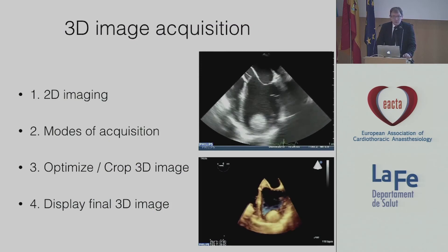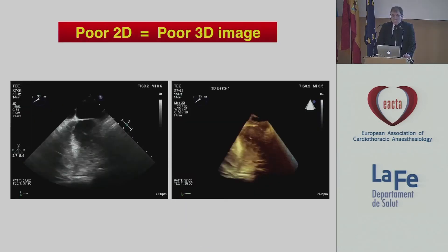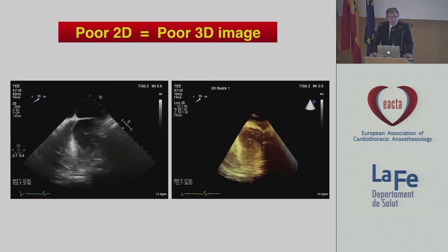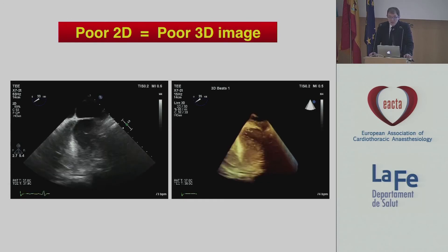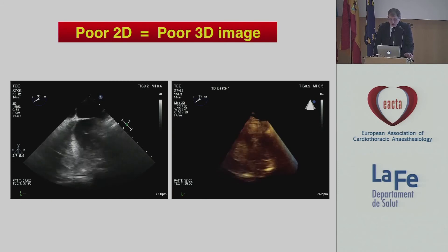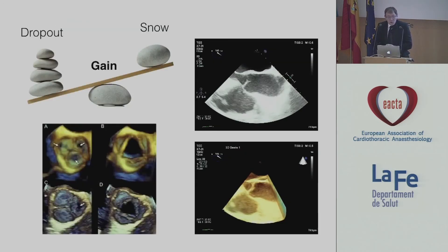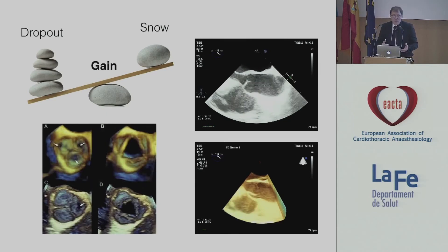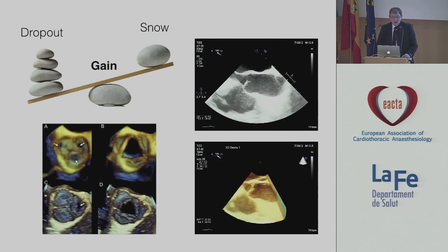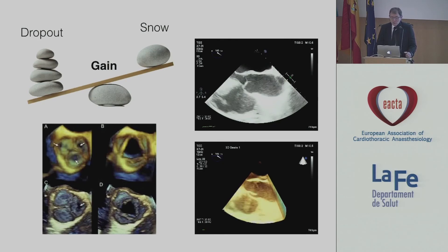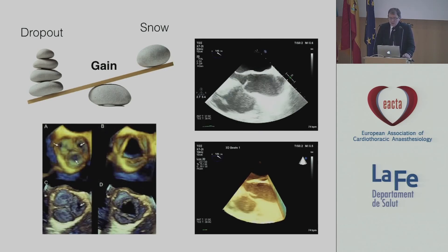This is a short outline of my presentation. Of course, the first thing you need to do before acquiring three-dimensional echocardiography data sets is to acquire good 2D images. Poor 2D images means poor 3D images. Try to optimize your two-dimensional images by adjusting the gain and the compression — it's a balance between under-gain, which gives you dropouts in 3D as you can see here pointed out with the white arrows, or too much gain, which gives rise to snow or a brownish smoke as you will see here.